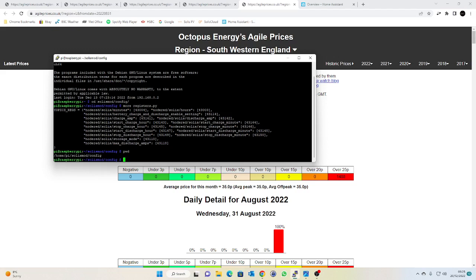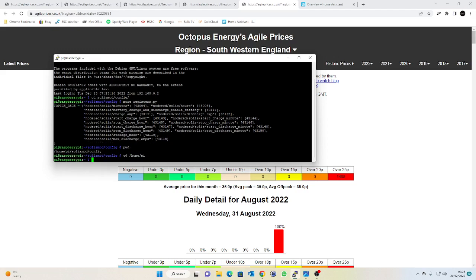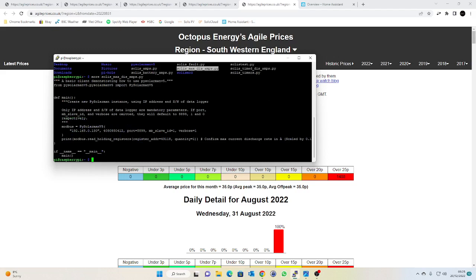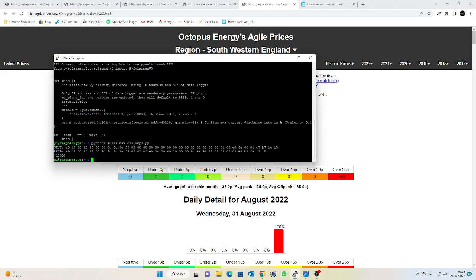So if I quickly show you using pysolarman the value of that register right now. I have a little pysolarman script called max discharge amps there we go, and in fact if I have a quick look at that we can see all it's going to do is print the value of register 43118. So if we run that little pysolarman script we can see right now that the max discharge amps is 1000 so it's a factor of 10. So a value of 1000 in the register means that that is set to 100 amps which is the max discharge rate for the Fox ESS 5200.